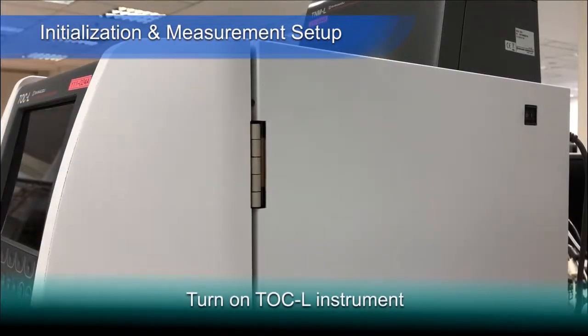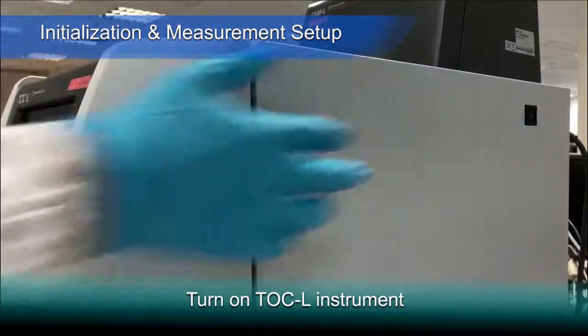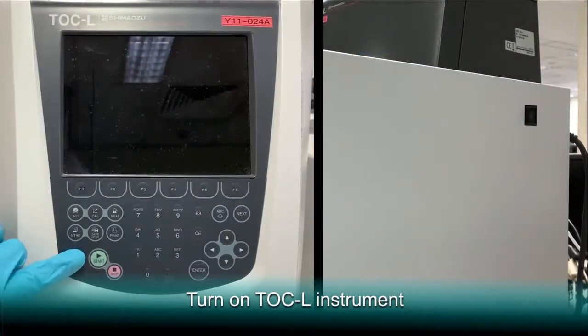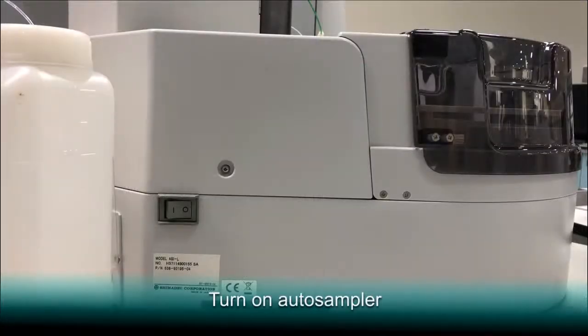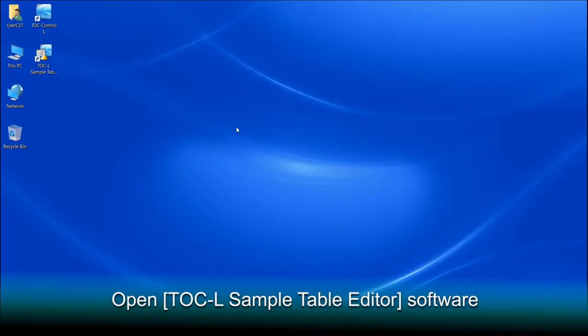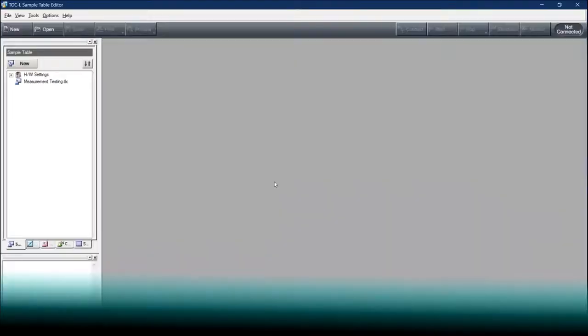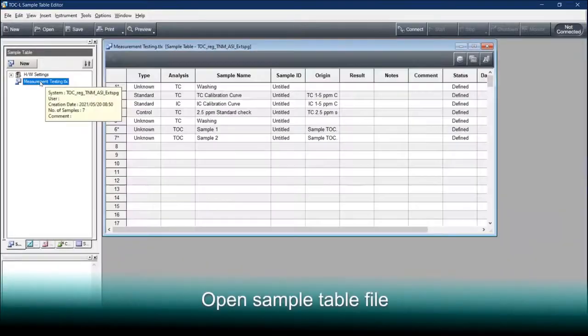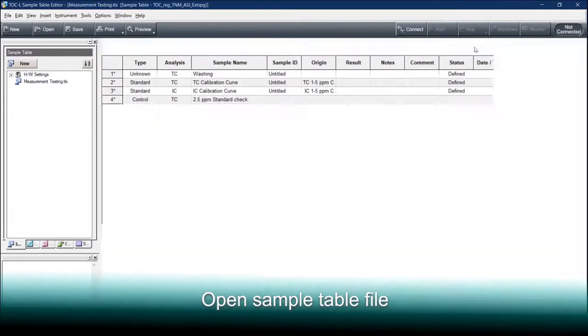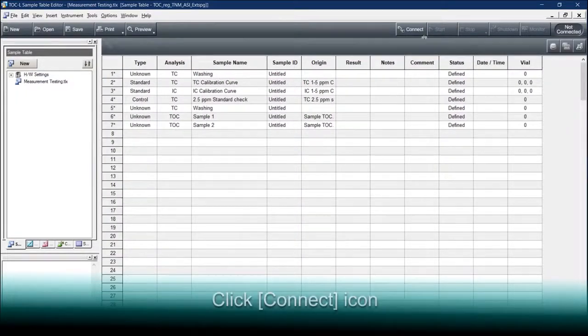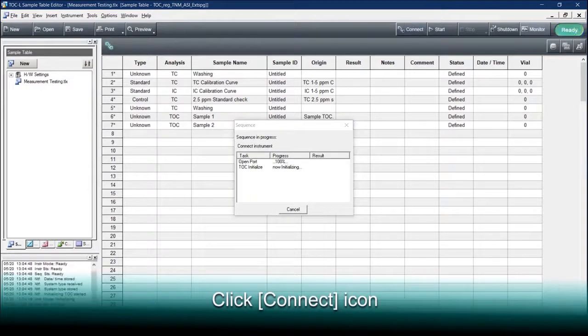We first start by turning on the power to the TOC L instrument. Since we'll be using the auto sampler for measurement, we'll turn it on as well. From the PC, we'll open the TOC L sample editor software, which is the software that controls the instrument. Open the sample table file that is used for measurement. Then, click the connect icon and wait for the instrument to be in ready state.